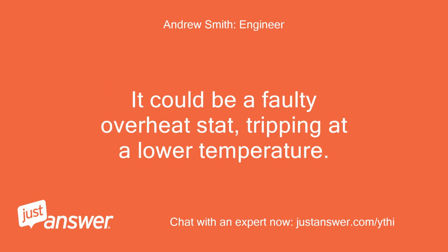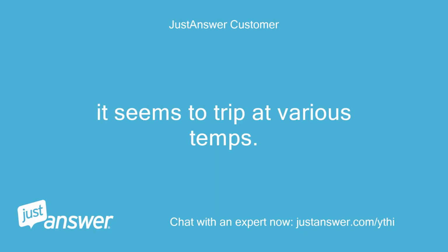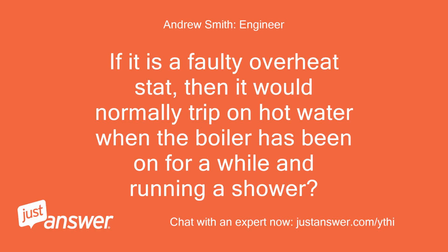Let's see if we can get you sorted in the shortest possible time. It could be a faulty overheat stat, tripping at a lower temperature. Are you able to check the temp it trips at? It seems to trip at various temps. I've tried adjusting the central heating temp and the hot water temp. If it is a faulty overheat stat, then it would normally trip on hot water when the boiler has been on for a while and running a shower.